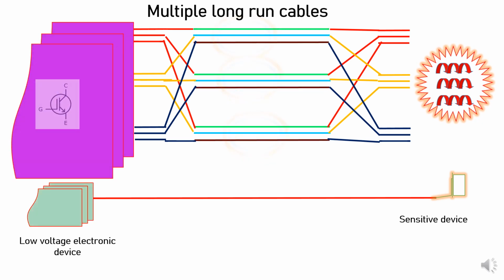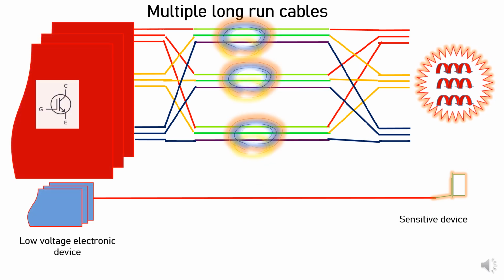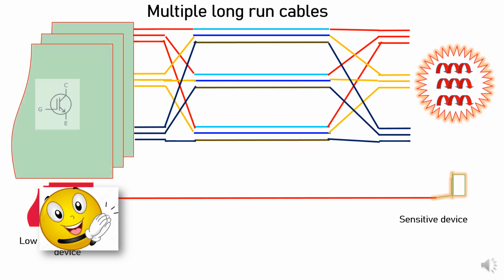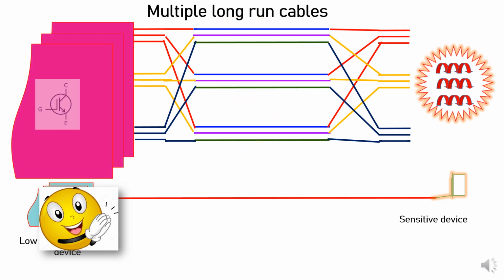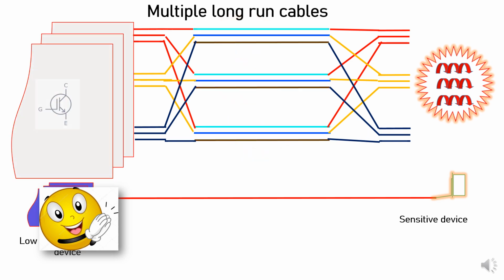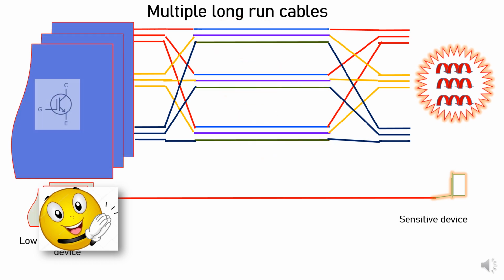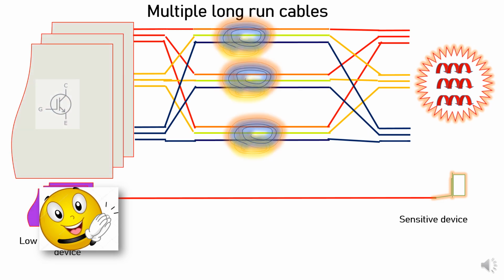Even though it's a sensitive device, your cable will be well protected, even running in parallel to the VSD run cable. So this is called a connection at the VSD end, and we have to change the cable connection, just as I have shown, so that it will cancel the effect of each and every field R, Y, and B. All the three will cancel each other's magnetic field, and at last it will nullify each other's effect. This is the first advantage of doing the cable connection at the VSD end as well as the motor end.